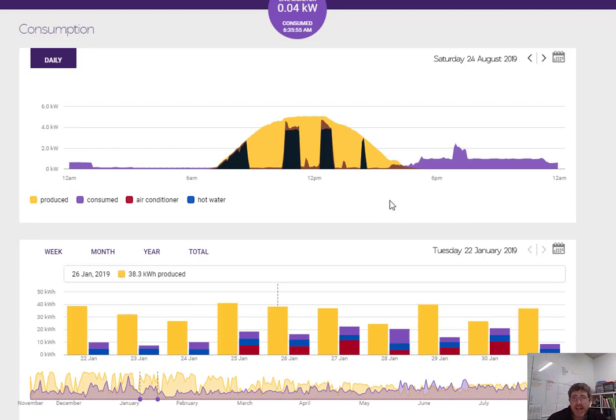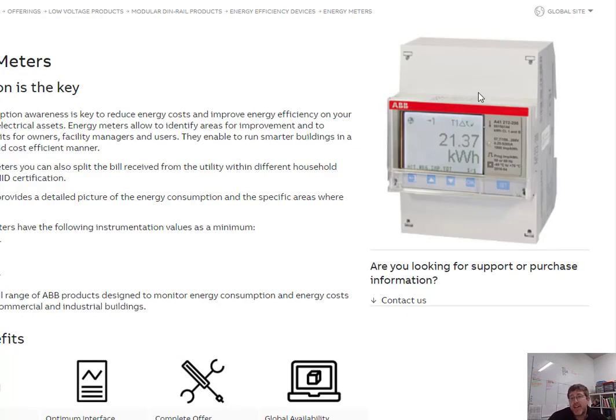One of the big reasons everyone does 5 kilowatt is that if you're in an urban environment, you can just whack up a 5 kilowatt and feed back. If you do put a 6 kilowatt up, it does add extra costs. You're required to add one of these things here called an energy meter. So with an energy meter, there's extra installation cost. This is designed to hold the inverter back, so it doesn't feed more than 5 kilowatts back to the grid. So if your inverter's producing 5 kilowatts and you're using 500 watts, your system's still going to produce and send 5 kilowatts back to the grid and you'll use the other 500.